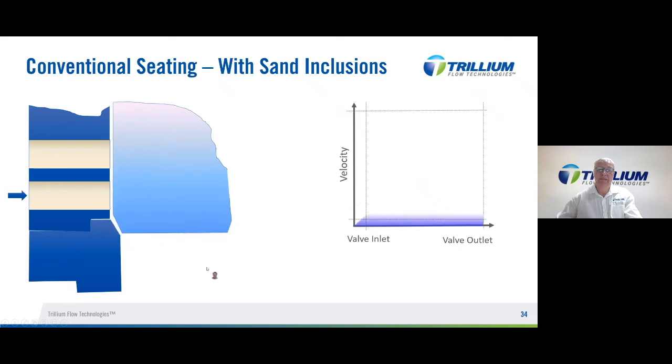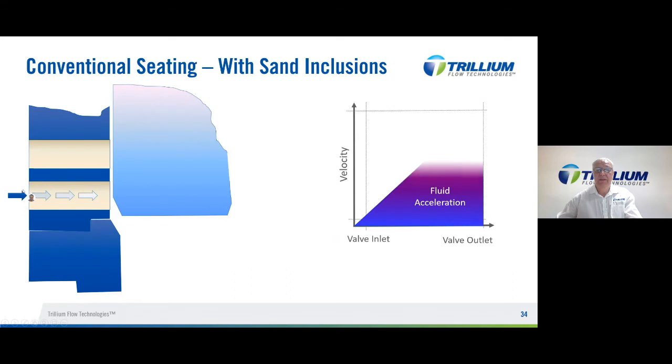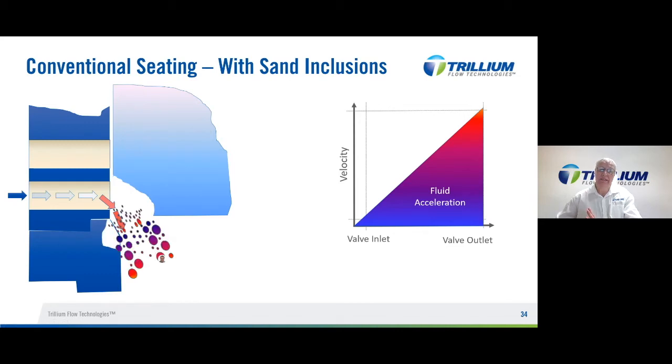But as the valve plug lifts up, the fluid can pass through between the plug and the seat. If the plug is close to the opening of the valve, this can potentially cause a higher velocity across the valve trim. Ultimately, this impingement of the fluid and solid particles can generate erosion of the seat, so that next time the valve is closed, you don't get a tight closure, and that equally can lead to further erosion. So considering the seating point, the seat angle is very important.